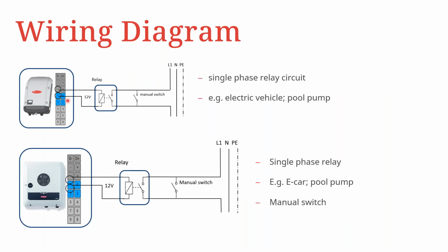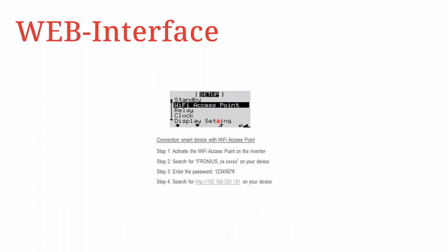When it comes to the configuration, for you to activate the IOs, you have to activate the Wi-Fi access point of the inverter. For instance, this shows the activation of the Data Manager's Wi-Fi access point. Then you follow the procedure for connecting to this Wi-Fi access point. And lastly, you would have to enter this IP address, which is common for all Fronius inverters. It doesn't matter whether it's a Snap inverter or a Gen 24 Plus. So 192.168.250.181. And then you are able to connect to the web user interface of that particular inverter.